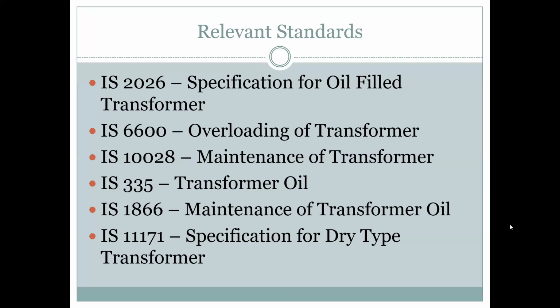But when we buy new oil, we don't get more than 35 to 40 kV. We have to filter that out. These are the mistakes made by the users. They think, I have got transformer oil in sealed drums, new, directly from the supplier, I can mix them and run these drums. This never should be. Even the new oil has to be filtered. This is a very, very interesting subject. People think, I have got new oil, so let us use it. It should not be.